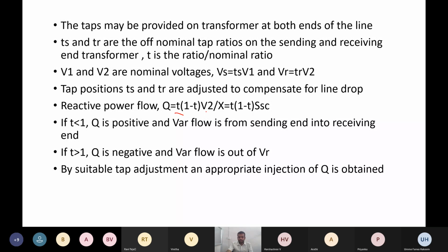So what is V square here? V1 and V2 are our sending end voltage and receiving end voltage. So by using that, Q, T. If T is less than 1, then the reactive power or VAR flow is from sending end to receiving end. So if the load requires reactive power, at that time T should be less than 1.